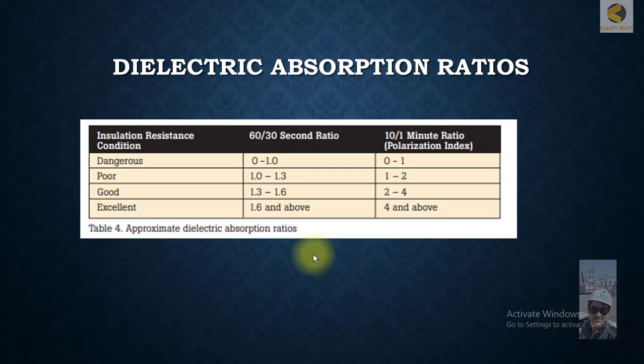When you take the readings, you can form different ratios. For example, you can have a ratio of 30 seconds to 60 seconds, and a ratio of 10 minutes to 1 minute, which is called the polarization index.